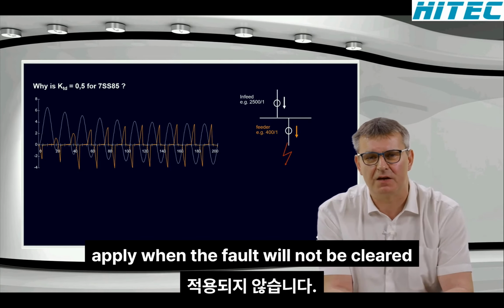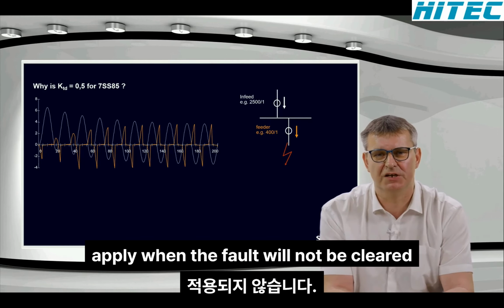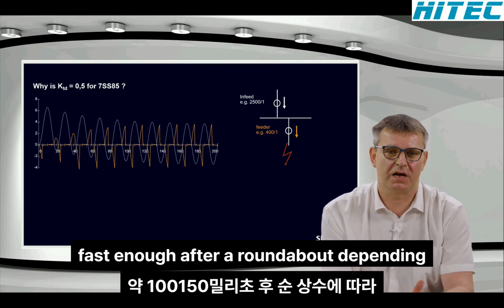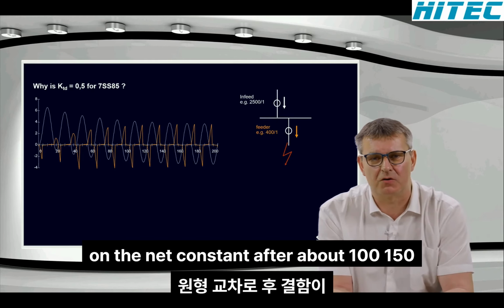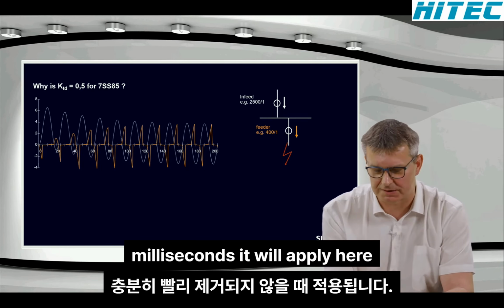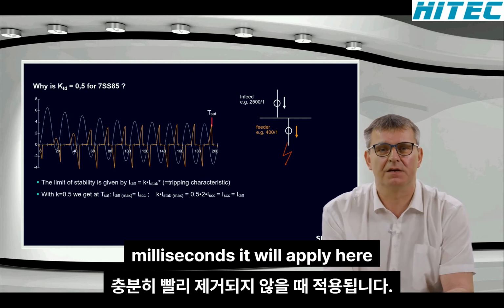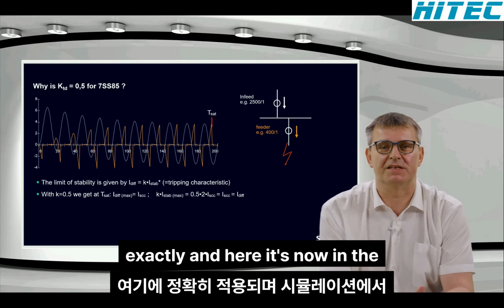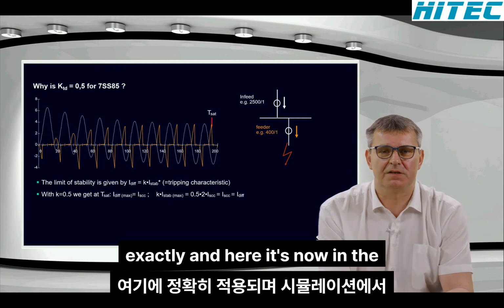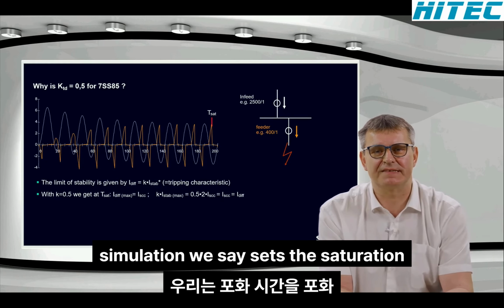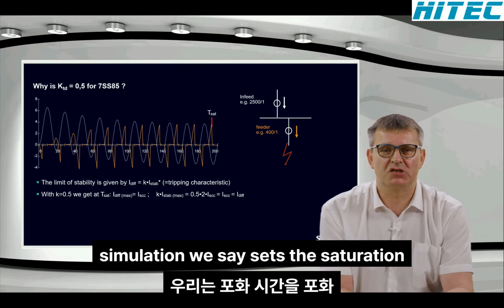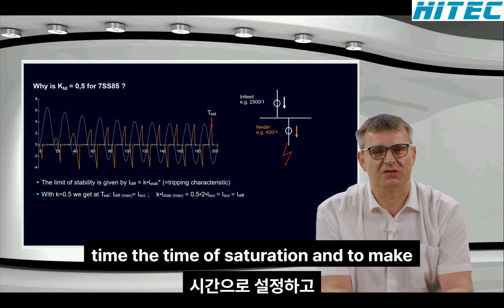It will apply when the fault is not cleared fast enough, after about, depending on the network time constant, 150 milliseconds. It will apply here exactly. And here, in the simulation, we say that's the time of saturation.